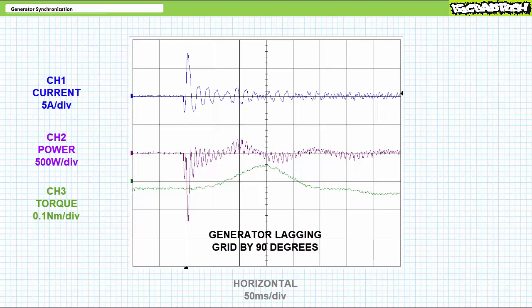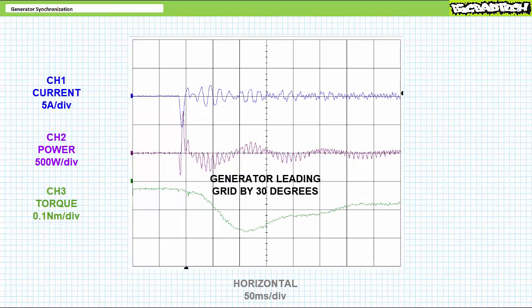Let's approach this from a different direction. What happens if the rotor is leading the stator at the time of closure? We should observe opposite effects. Consider what happens when I close the contactor when the generator matches grid phase shift, frequency, and voltage, however the rotor is leading 30 degrees ahead of the stator at the time of closure. Electrically, there's a momentary surge of current and electrical power out of the machine, and mechanically, the shaft experiences a surge of counterclockwise torque against the previously established clockwise direction. The rotor's ahead and the grid says 'not so fast' and pulls it backward, as would a brake. Not the ideal scenario, but all in all, not too bad.